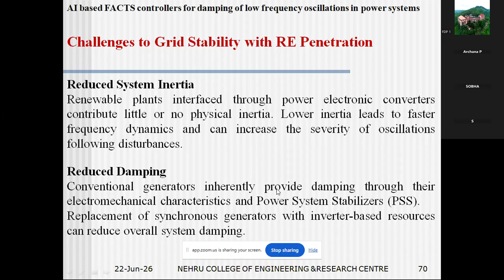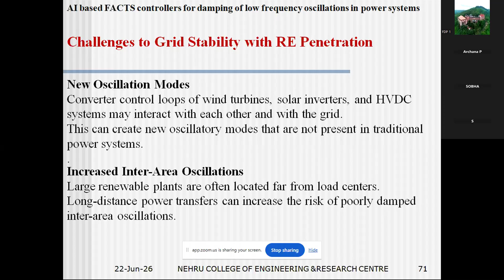New oscillatory modes have developed. Converter loops, control loops of wind turbines, solar inverters, and HVDC systems will interact with each other. We discussed control modes, torsional modes, local modes, then inter-area modes. Now there are new modes of oscillation which are not present in a traditional power system, so modal analysis is required on how to address them. And increased inter-area oscillations: large renewable plants are far from the load center, so power has to travel through long distances, giving poorly damped inter-area oscillations. So we can say there is a very imperative threat of low frequency oscillations because of more and more renewable penetration, and there is a need for more serious studies on how to damp these oscillations. New researchers should come up with solutions for this.